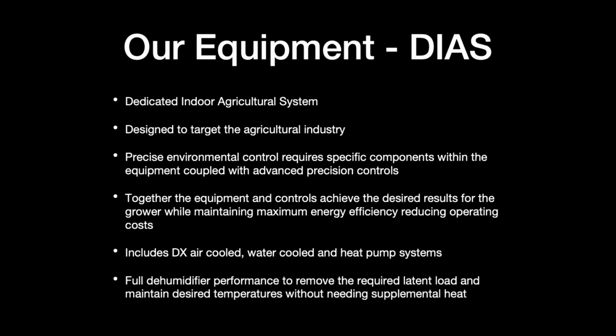And then we use recovered energy, recovered heat to reheat that air to maintain temperature. So we're really minimizing the energy required to what's required to remove the moisture. Once we've removed the moisture, we have enough recovered energy to then maintain our temperature.